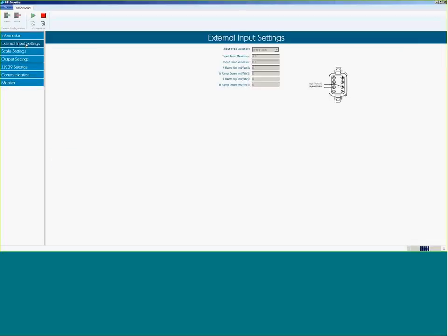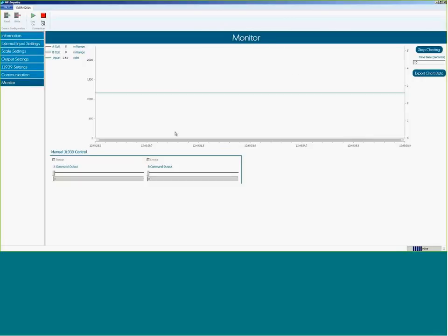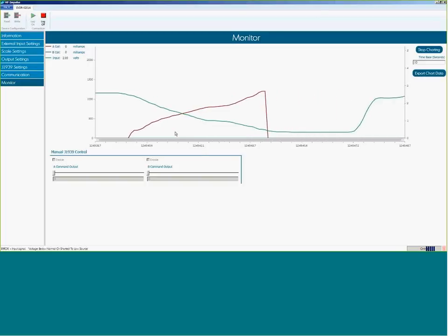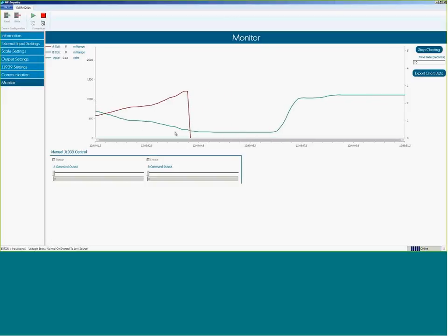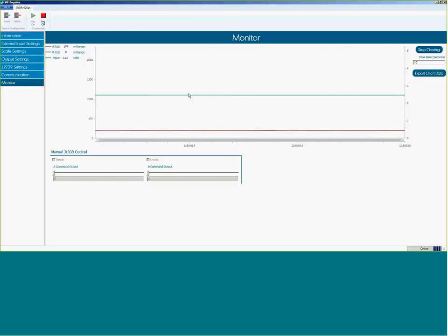You may recall we set up errors, both maximum and minimum of the input error. So I monitor the analog input. If it reaches half a volt, I'm going to kill it because that's considered an error condition, sending back neutral, which is about 2.5 volts. The errors will not go away until you cycle power, for safety. I'll turn my power supply back on again and go back online.